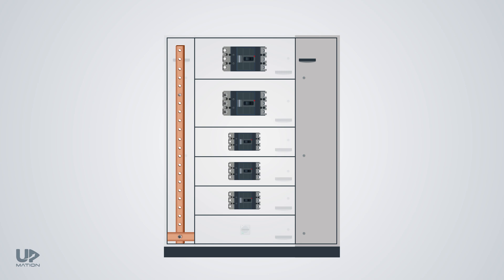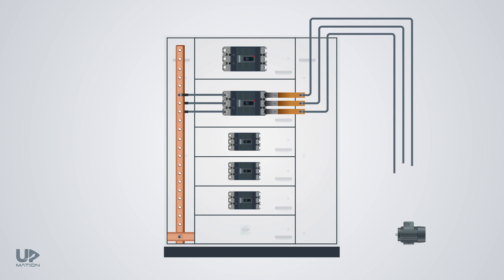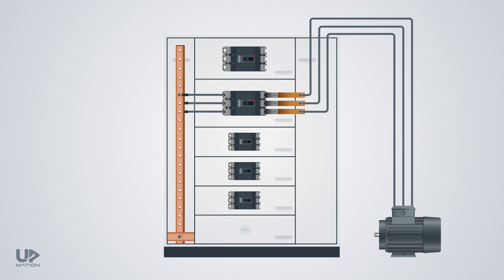These circuit breakers take the power from the bus bars, and in the right-hand side compartment, the cables will be connected to the output of the circuit breakers and transfer the power to the electric motor terminal box. This electrical MCC panel is actually a kind of side baying system in that separate panels are connected side by side.